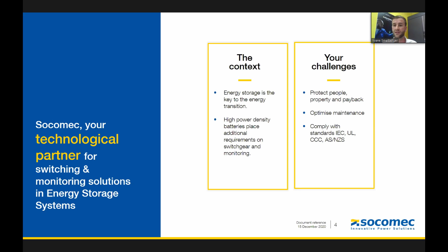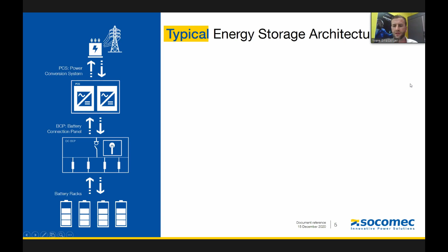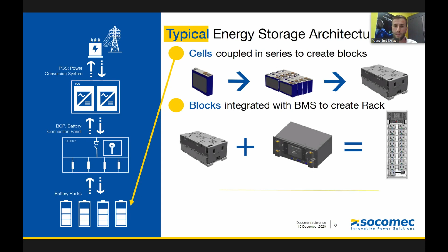So when we look at a typical energy storage architecture, which I will use for today's purpose, I will look at battery racks feeding into a battery connection panel or BCP, one step higher into my PCS, my power conversion system, and then back into my grid. So typical AC coupled system, just to make it very simple. Now to make my point, when we take cells and we integrate these cells into a rack together with a BMS system, one rack could potentially have a prospective short circuit current of up to 10,000 ampere, which is high, but it's not something unseen in a distribution board in a residential application.